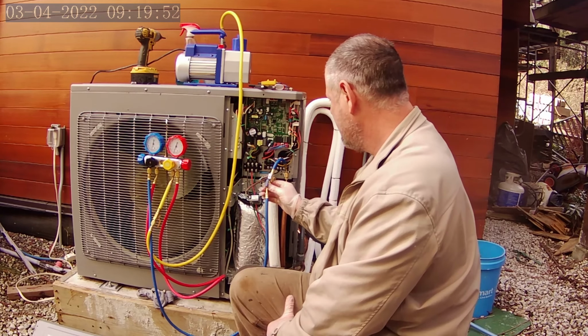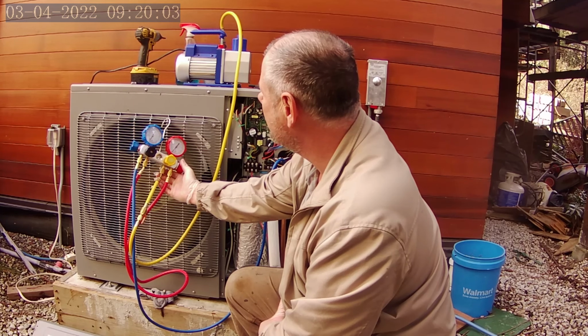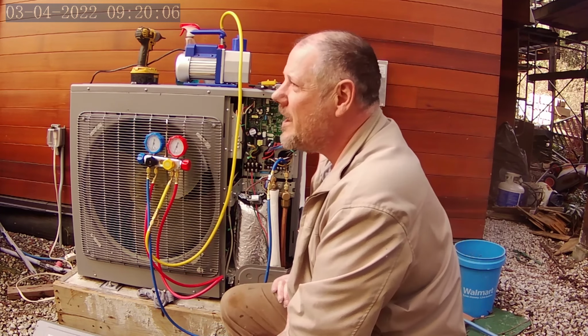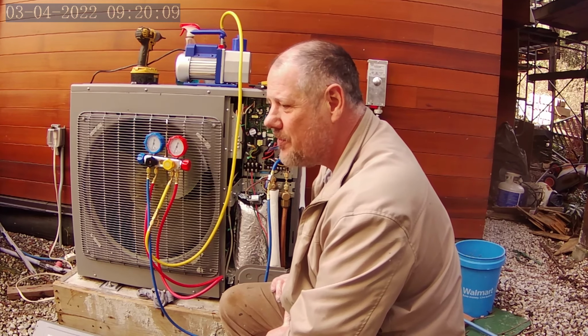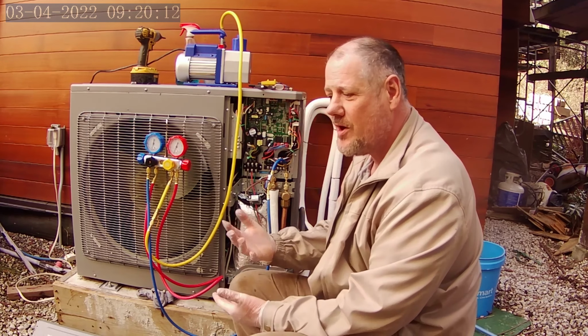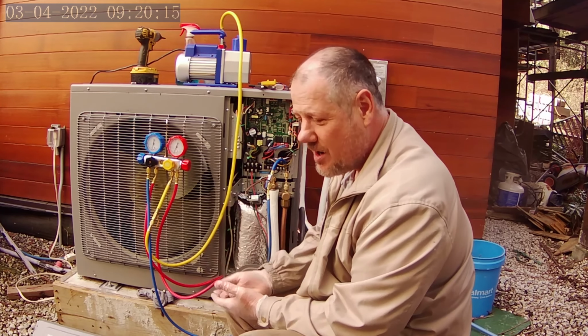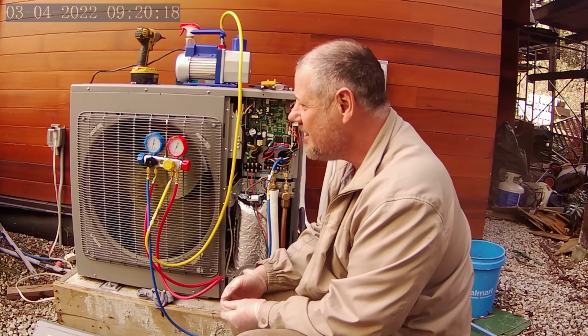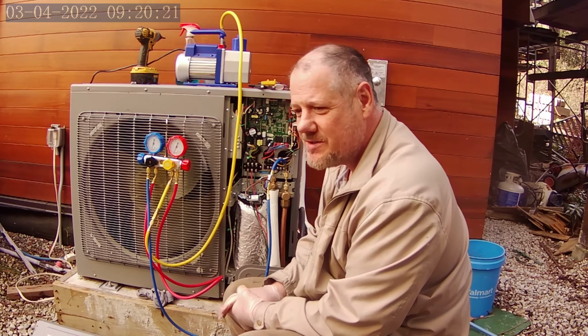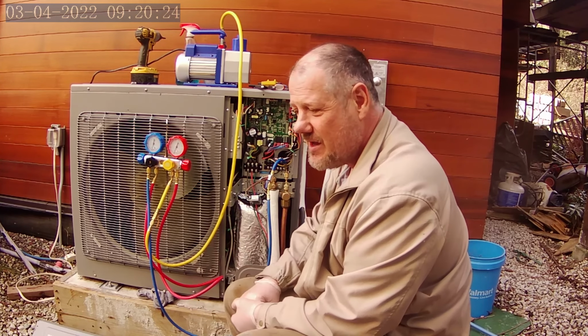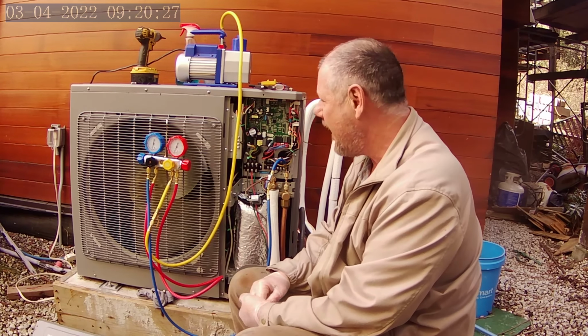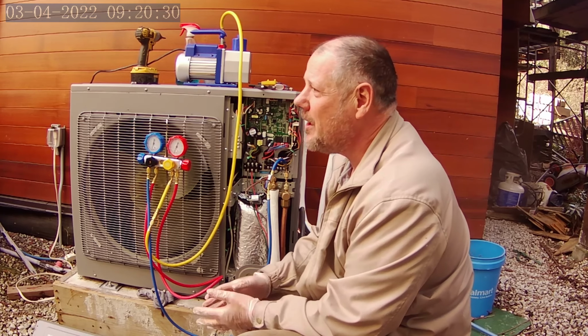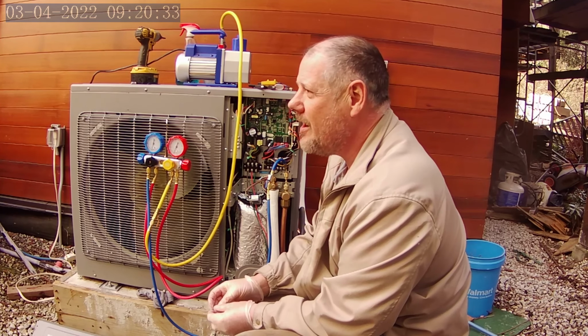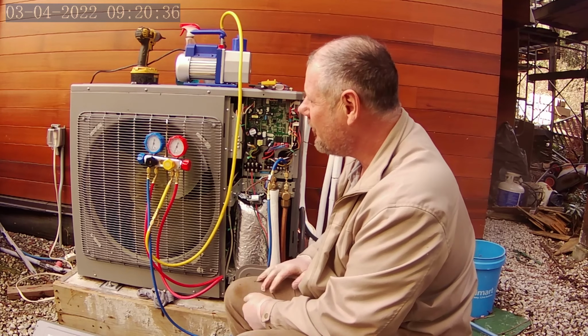So what we're seeing now is about negative 29, but you want to just keep running it for a couple of hours. You want a really deep vacuum. Make sure you've evacuated all of the moisture, argon, or normally it would be nitrogen, any oxygen molecules. You want to get rid of basically any molecules of anything in the system and just have straight vacuum. That way you're not going to contaminate the refrigerant oil that comes out later on.